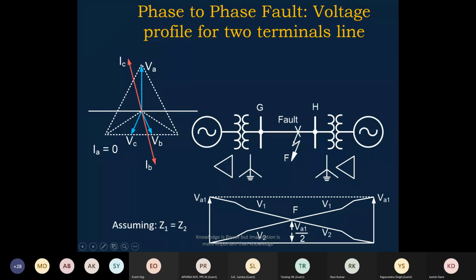Similarly, you look at it here. So when there is a fault location F, the positive sequence component is almost divided by 2. When you go far away from this, the positive sequence voltage is getting increased, the negative sequence voltage is getting decreased.